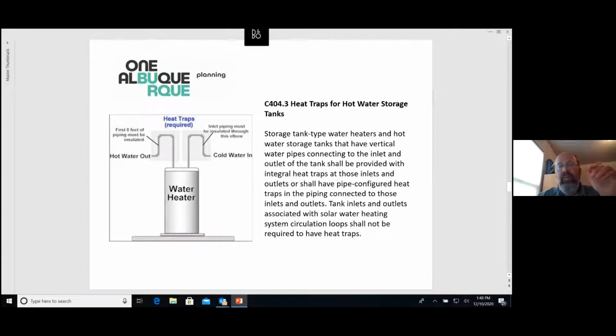And then the first 8 feet of piping must be insulated. The inlet must be insulated through the elbow shown there. That's to keep more warm water where it's supposed to be. This is on the vertical inlets, so as illustrated, the outlets on top of the tank type water storage tank. Side outlets, you're going to have a different issue. You're not going to have this because the heat isn't rising like that.